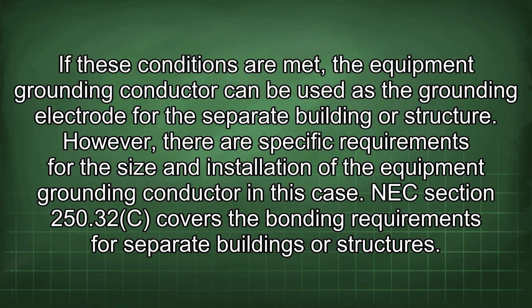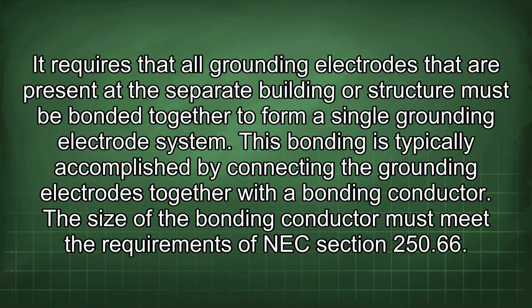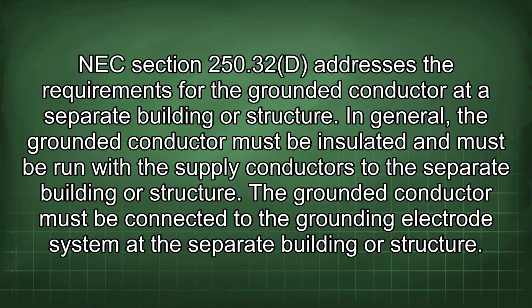NEC Section 250.32c covers the bonding requirements for separate buildings or structures. It requires that all grounding electrodes that are present at the separate building or structure must be bonded together to form a single grounding electrode system. This bonding is typically accomplished by connecting the grounding electrodes together with a bonding conductor. The size of the bonding conductor must meet the requirements of NEC Section 250.66.